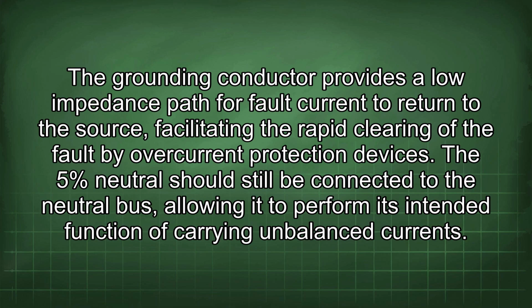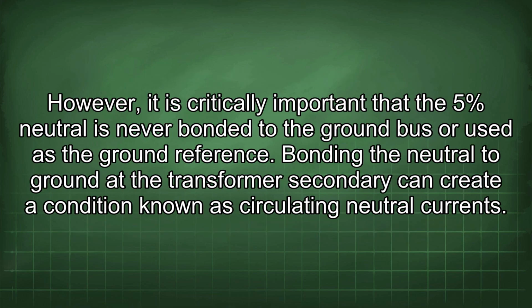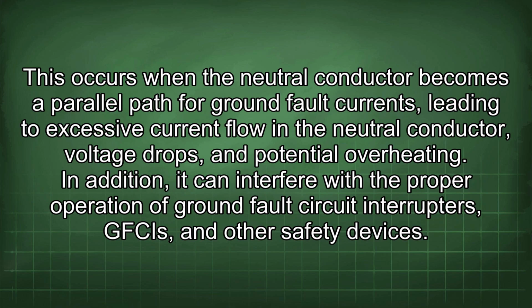The 5% neutral should still be connected to the neutral bus, allowing it to perform its intended function of carrying unbalanced currents. However, it is critically important that the 5% neutral is never bonded to the ground bus or used as the ground reference. Bonding the neutral to ground at the transformer secondary can create a condition known as circulating neutral currents. This occurs when the neutral conductor becomes a parallel path for ground fault currents, leading to excessive current flow in the neutral conductor, voltage drops, and potential overheating. In addition, it can interfere with the proper operation of ground fault circuit interrupters, GFCIs, and other safety devices.